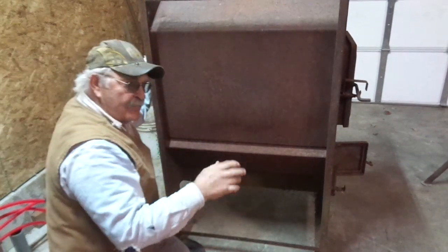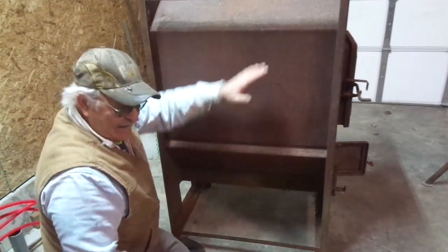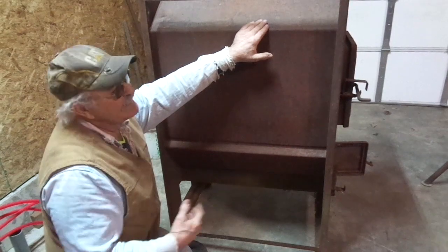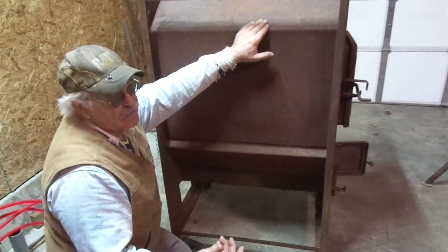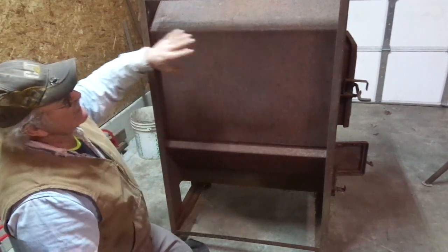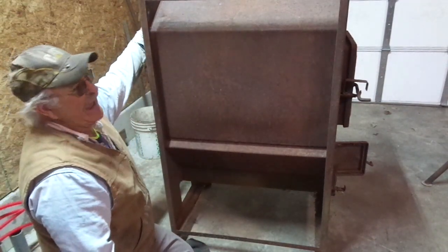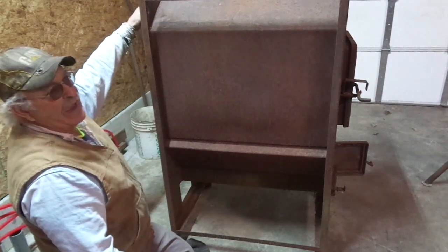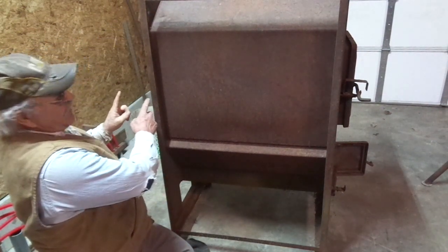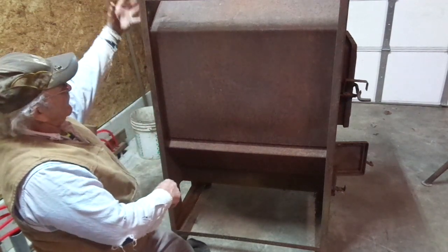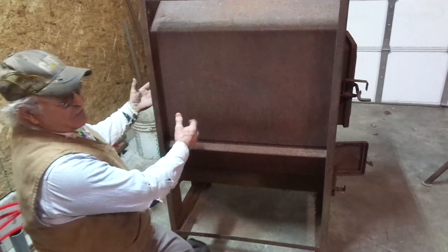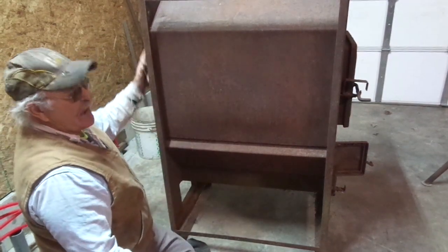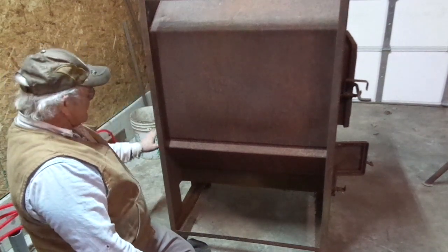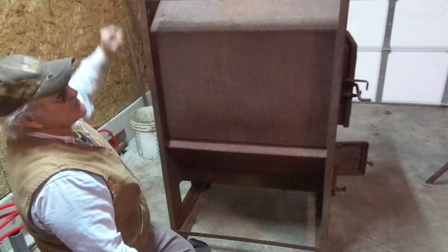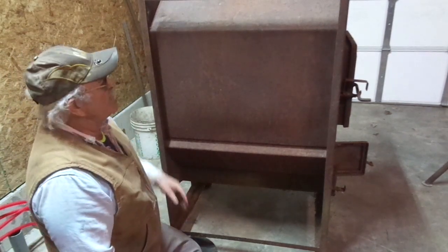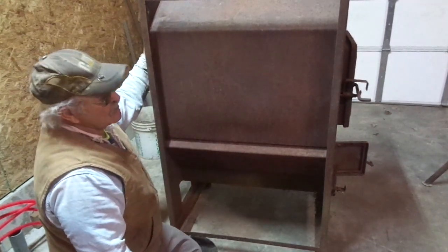Again, we're kind of arguing semantics. I like to refer to it as a secondary heat exchanger, even though some people can argue that it's not. Typically a secondary heat exchanger would be another compartment that goes off the back end where it enters up high, and then it's a narrower heat exchanger, 4 or 5 inches thick, and it will get all nice and hot in here, and it'll be encompassed in the plenum, and then the extra heat is extracted off of that secondary heat exchanger before it passes out the lower exit level and up the chimney. So you extract a little more heat from the burned flue gases before it goes up the chimney.